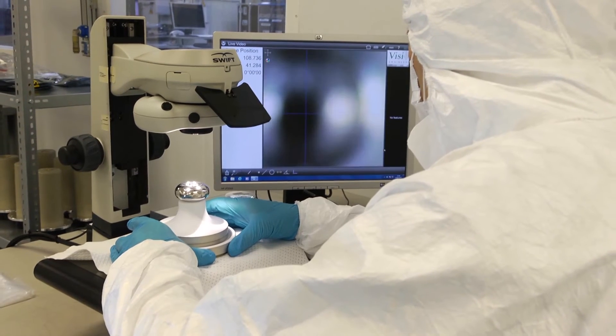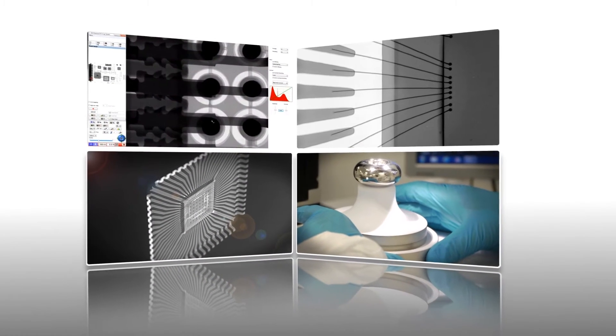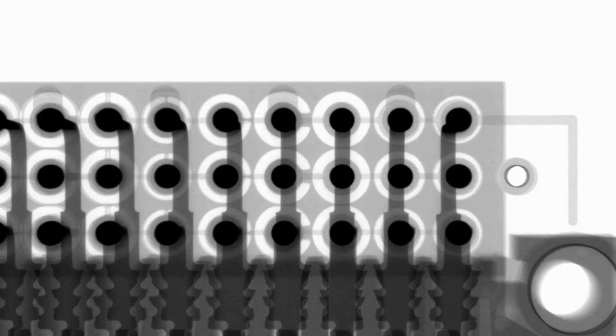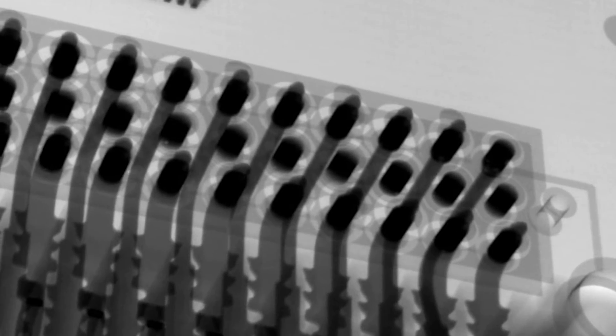We're going to have an open tube technology — we've taken open tube technology rather than our sealed transmissive tube technology, but we've significantly improved it to give a unique offering. The filament life of our systems is longer than the marketplace is currently able to produce. The vacuum is higher, the x-ray beam is more focused, and this leads to a better quality image on the screen.